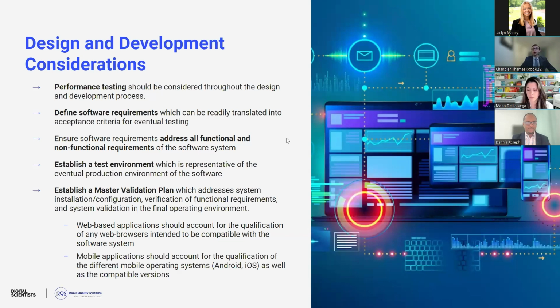So if you're, for example, claiming compatibility with iOS 14 and beyond, FDA is going to want to see that you've accounted for this in your test plan and proven that iOS 14 is compatible, as well as all of the other versions. And this is done from release notes review, making sure that the release notes for each of the operating system version updates is not going to have a negative impact on any of your testing. Identifying particular versions that you want to incorporate in your test plan.